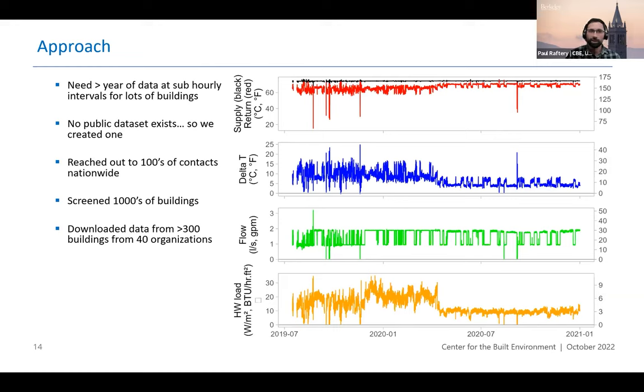Looking at the same building but showing the actual measured load on the boiler — on the water side, not the gas side — there's a high morning winter peak on the right-hand side and a low baseline load throughout the summer. But if you remember, we measured standby losses or distribution losses in seven other buildings, and effectively most of the boiler load during the summer — the majority of it — would be covered by that average distribution loss we measured. In other words, the boilers are operating in summer predominantly just to heat up the hot water system, as opposed to any genuine need in the building. And bear in mind, we are paying for chilled water to actually reject those heat losses out of the building, so it's a double penalty.